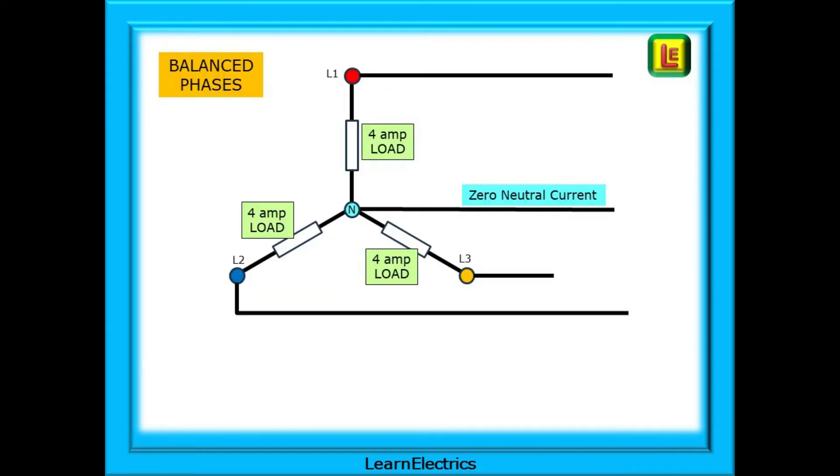Let's look at that in pictures. With balanced phases, 4 amps flows through the load on each phase. This might be motor windings, as an example. As a result, there is zero neutral current. This is why some motor circuits are four-wire only, three phases plus earth, with no neutral in the cable.